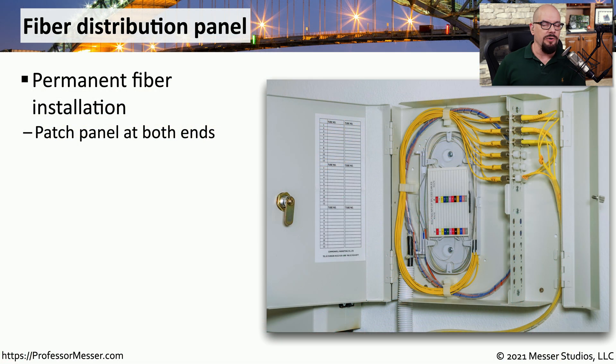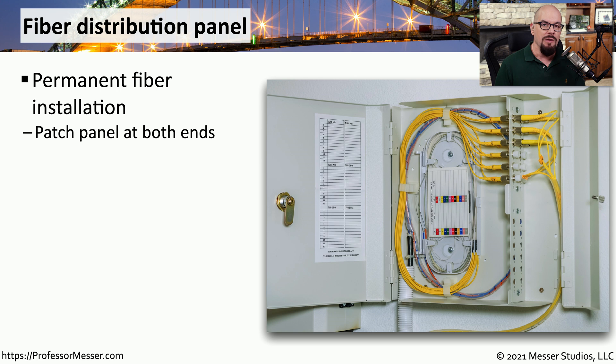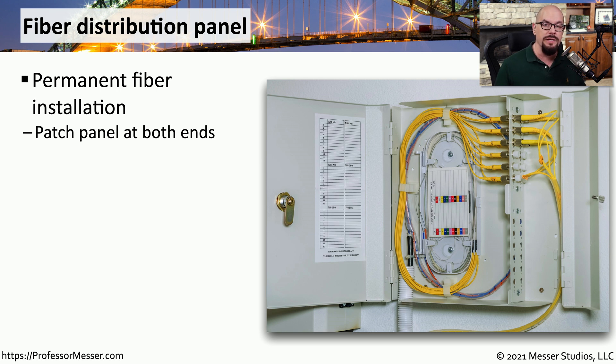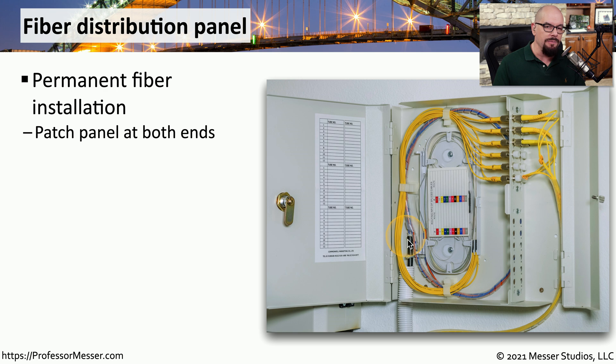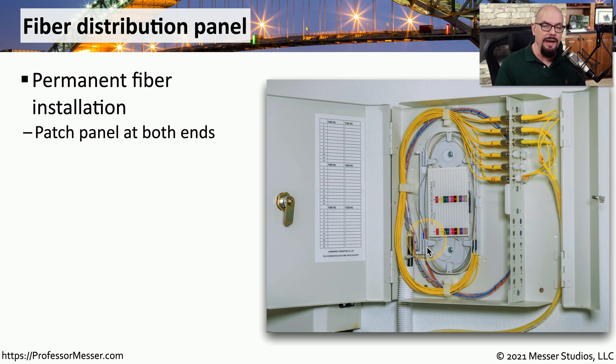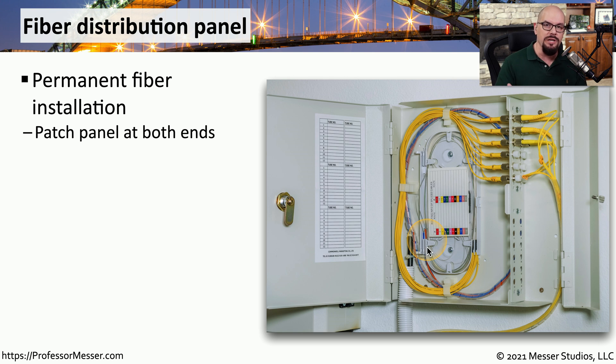We don't tend to run fiber connections from someone's desk, generally due to the expense associated with installing fiber, but we will commonly run fiber between floors of a building or between separate buildings themselves. On both sides of that fiber run, we will often install a fiber distribution panel, because we rarely run a single pair of fiber between connections. If we're going through the cost and expense of running that fiber optic connection, we will generally run more than one fiber at a time.